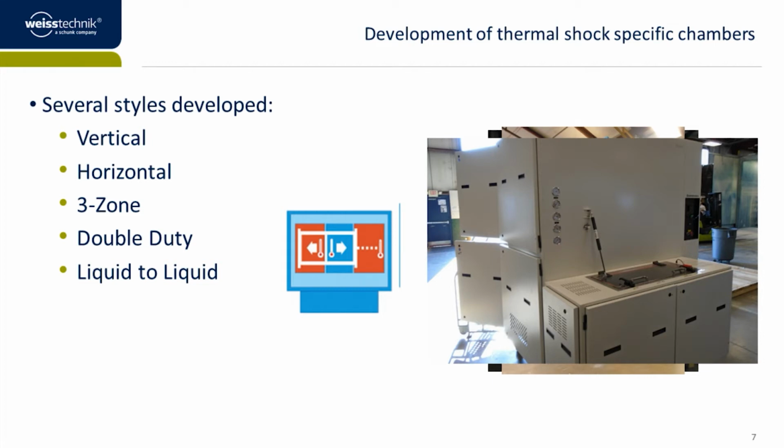And when it moves right, it exposes the basket to ambient conditions. So it still holds true to that original thermal shock spec. But everything moves in a very reliable and time-precise method. So if you need 30 seconds, it'll transition in 30 seconds, and it'll sit there for 10 minutes or whatever your set points are. So some customers still use this, and we are able to supply that.